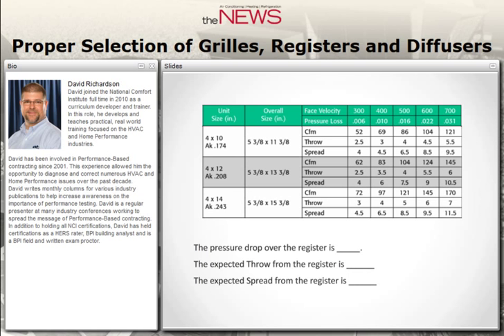The expected spread from the 4x12 register is 7.5 feet at 50 feet per minute terminal velocity. As a design rule of thumb, shoot for a terminal velocity that reaches about 75% of the ceiling height. If you're trying to cover a pretty good area without needing a lot of throw, this is a great register. But if you're trying to throw air long distances with less spread, you may want to look at a different register for that application.